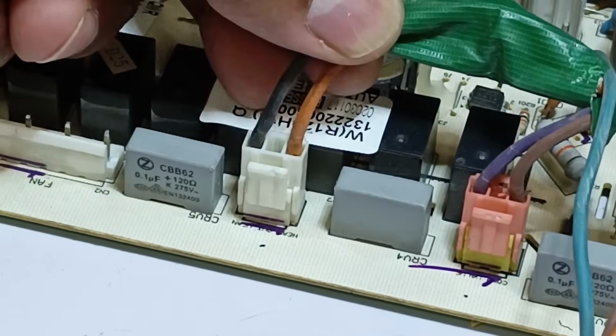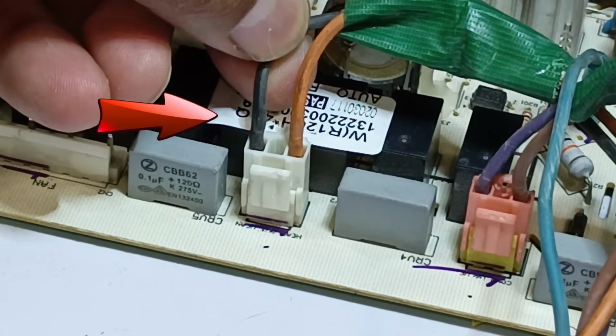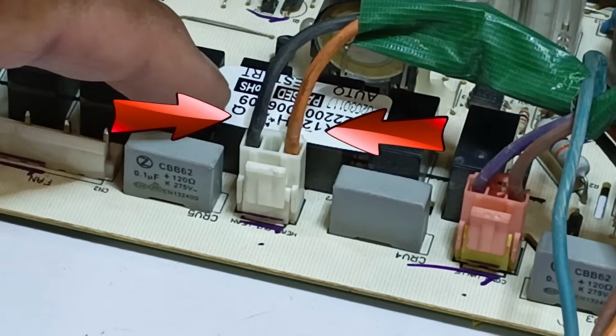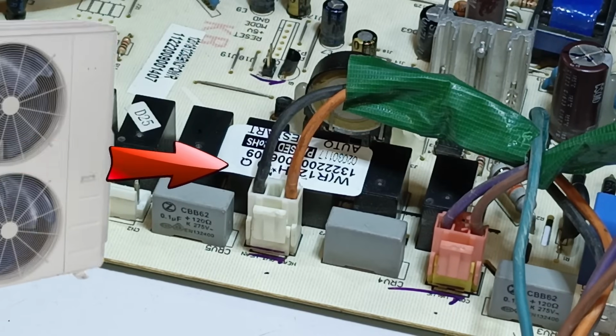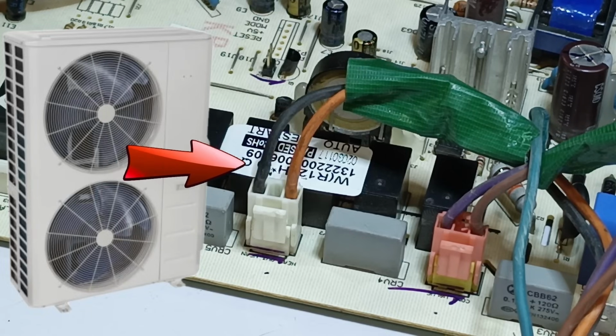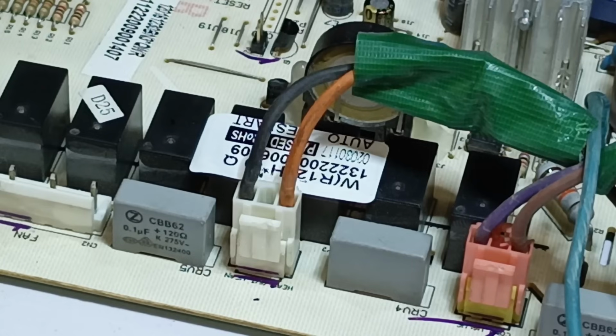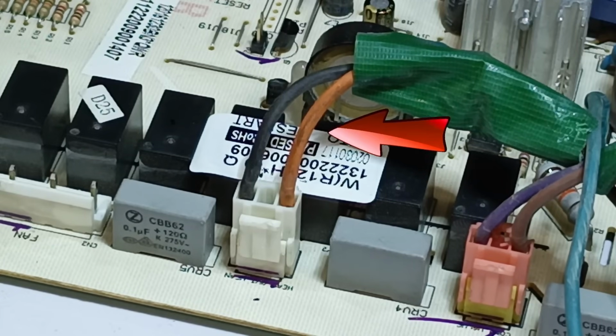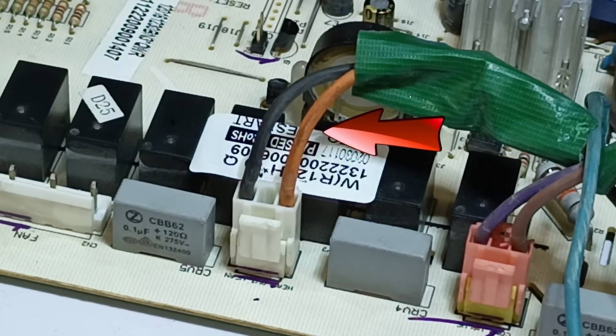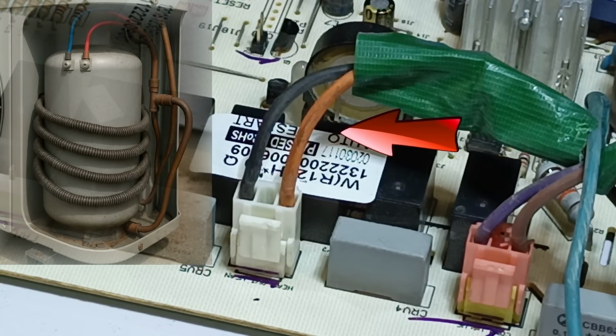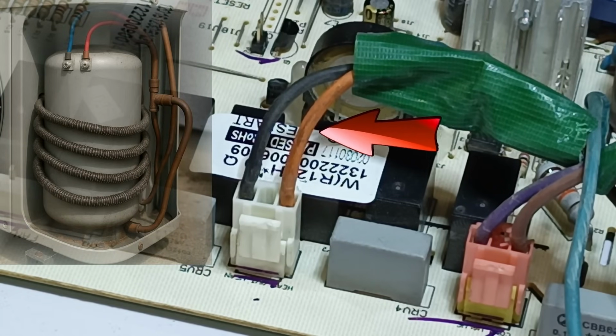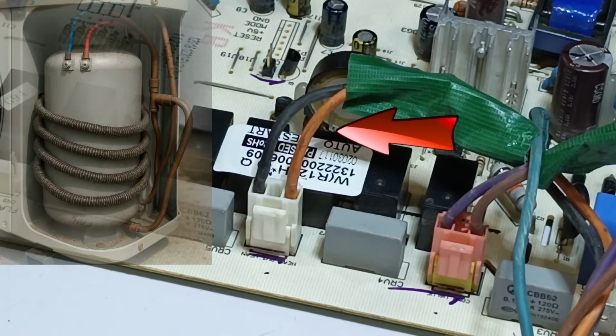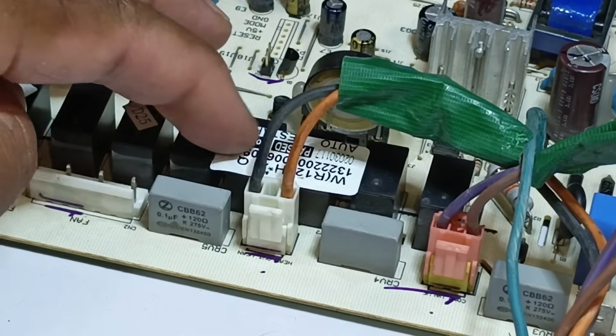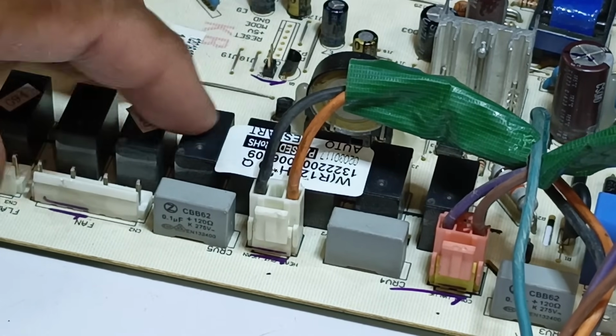Here you can see these 2 wires. One is orange, and the other is black. These 2 wires are controlled by relays. The black wire is used to power both fans, which run simultaneously. Once the system detects that the cooling process is complete, it turns both fans off. Then comes the orange wire, which is connected to a heater, either inside or mounted on the compressor. This heater is used in rare situations, such as when excess liquid has entered the compressor. The heater helps to evaporate that liquid, so the system can convert it back into gas and resume normal operation. All of these relays are controlled by the microcontroller on the circuit board.